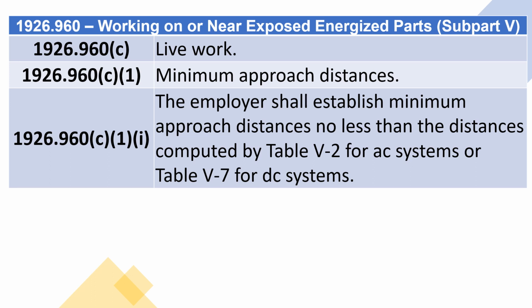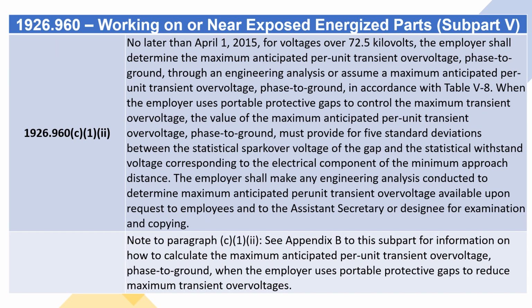1926.960(c) Live work. 1926.960(c)(1) Minimum approach distances. 1926.960(c)(1)(i). The employer shall establish minimum approach distances no less than the distances computed by Table V-2 for AC systems or Table V-7 for DC systems. 1926.960(c)(1)(ii). No later than April 1, 2015, for voltages over 72.5 kV, the employer shall determine the maximum anticipated per-unit transient overvoltage, phase to ground, through an engineering analysis or assume a maximum anticipated per-unit transient overvoltage, phase to ground, in accordance with Table V-8.